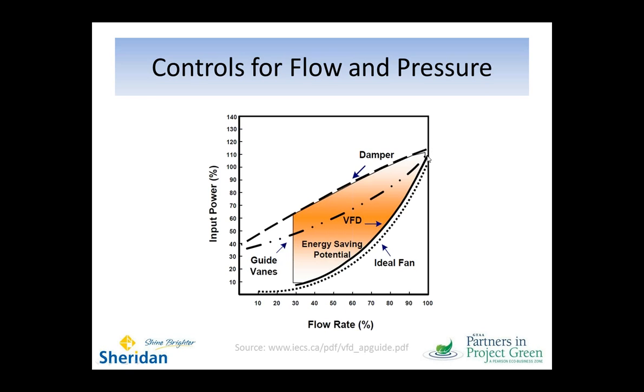Compare this to a variable frequency drive, which scales down in this nice curve so that my 50% flow rate is now at about 20% of the input power. And all of that orange space in the middle is my energy saving potential by picking the right kind of control for that application.